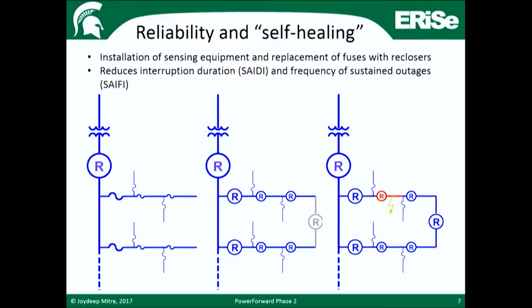We're trying to move away from fuses and put in more reclosers. If you look at the center figure, we've replaced a few of the fuses with reclosers. It's expensive to replace all fuses with reclosers, so on a few key feeders we've done that. At the end, on the right side, there's a grayed out link between the top feeder and the bottom feeder, a link that did not exist in the traditional figure on the left. That recloser ties the two feeders, and that's one aspect of distribution automation.